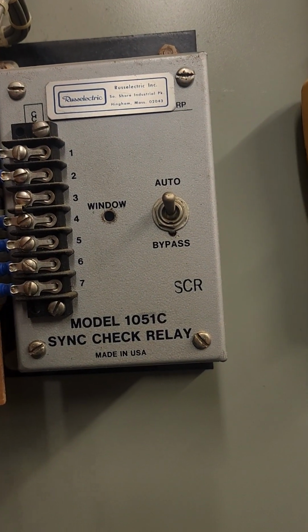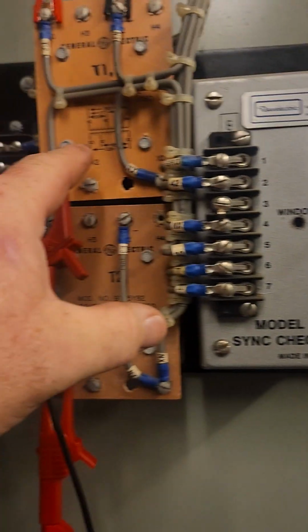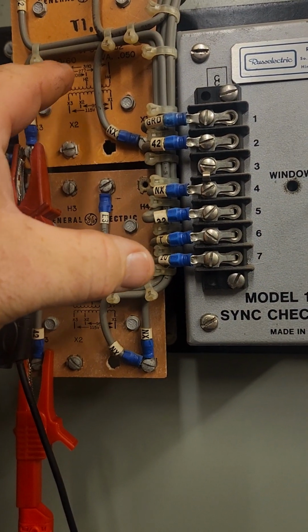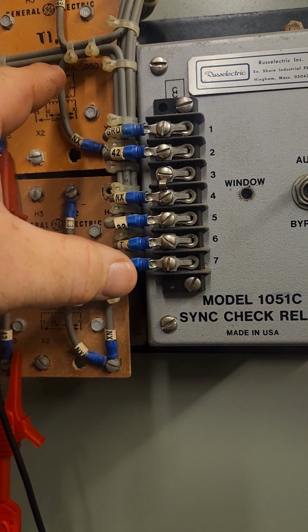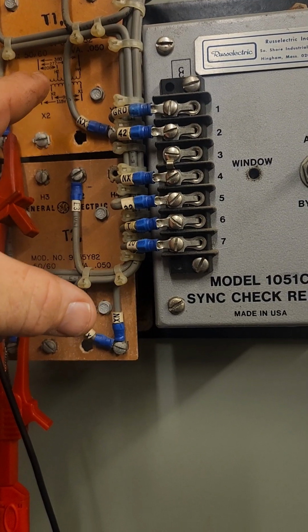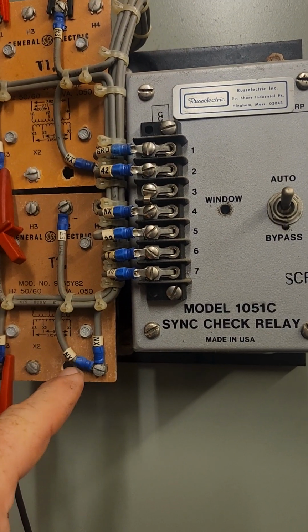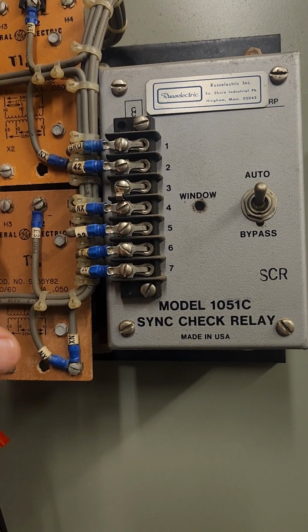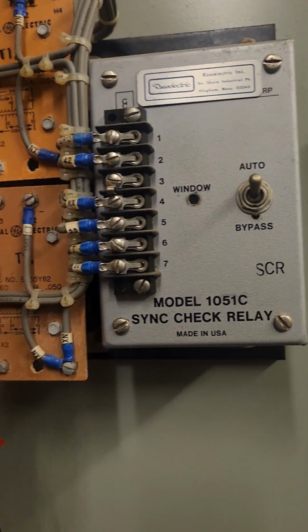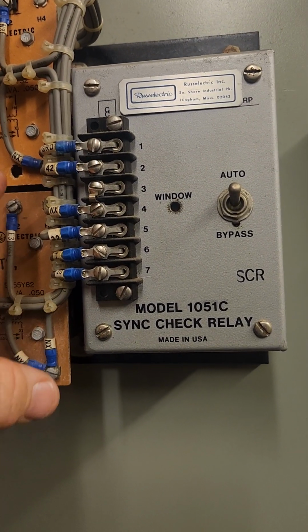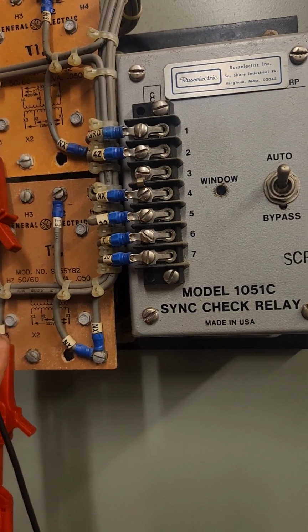They're reading, so basically if you follow, let's say X3, we go through the coil load side of the normal transformer, since X1 and X are tied together. So start with 32, that's one leg of normal, goes through the coil, comes down, comes back through this coil, and then goes to 42.